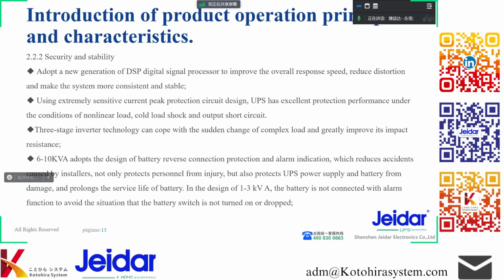6 to 10 kVA adopts the design of battery reverse connection protection and alarm indication, which reduces accidents caused by installers, not only protects personnel from injury, but also protects UPS power supply and battery from damage, and prolongs the service life of battery. In the design of 1 to 3 kVA, the battery is not connected with alarm function to avoid the situation that the battery switch is not turned on or dropped.